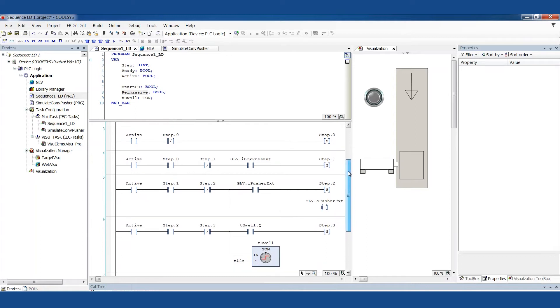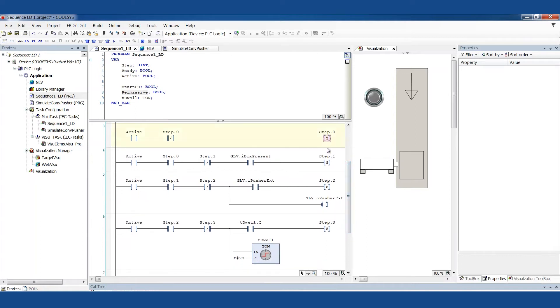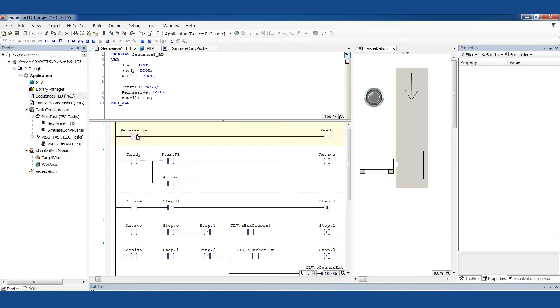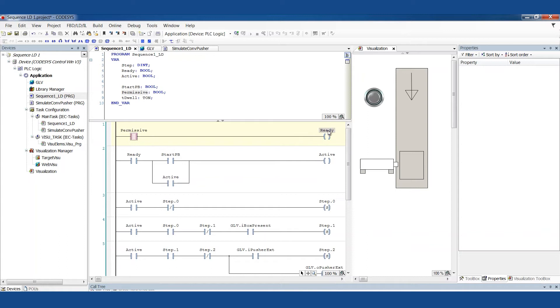Something that you'll find to be true in any iteration of a sequence is that you're going to try to have steps. Often they're numbered. Maybe you give them names. And those steps, you're going to want to keep as similar as possible. You want to keep the same structure. In this case, I've got step zero, step one, and step two. You'll notice they all share a pretty similar structure. We also generally have permissives. When is this sequence allowed to run?